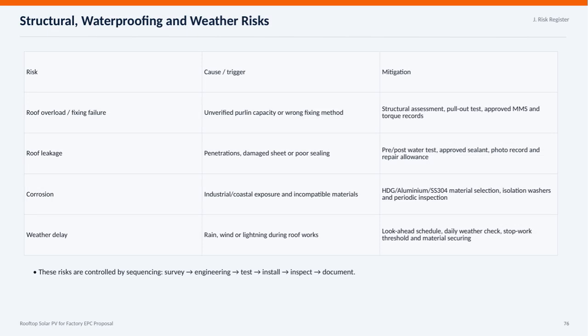Here we have several key risks associated with rooftop solar PV installations on factories, specifically focusing on structural, waterproofing, and weather-related challenges. First, roof overload or fixing failure can occur if the purlin capacity is unverified or if the wrong fixing method is used. To mitigate this, we conduct a thorough structural assessment, perform pull-out tests, and ensure all fixings are approved with torque records.